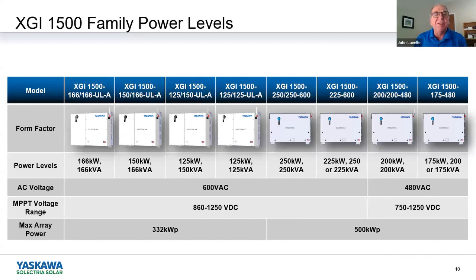Here's a snapshot of the lineup. The first 6 machines from left to right all have a native AC output of 600 volts. These absolutely require a transformer to hit whatever medium voltage you'll be connecting to on the AC side. The 2 machines on the right-hand side of this slide might be the most interesting for RENVU installer customers, in that the 175 and the 200 have a native AC output of 480 volts. So what that means is you can do a ground mount right into a load at 1500 volts with no need for a transformer.